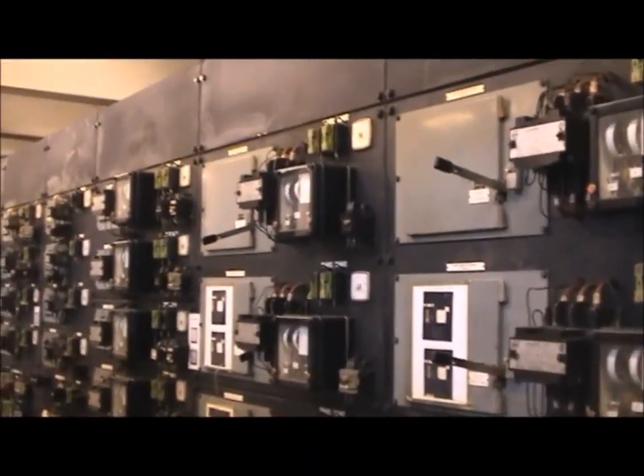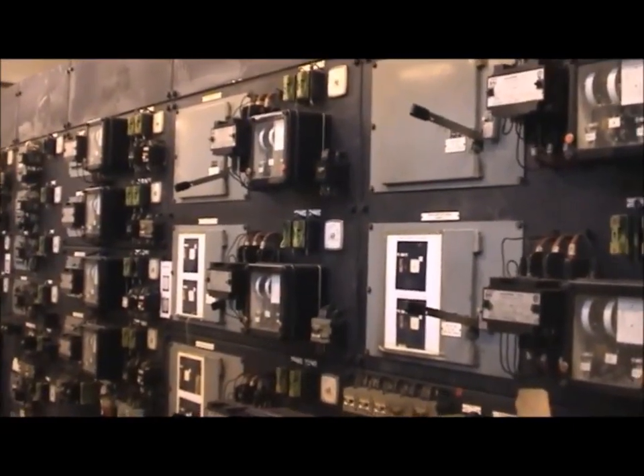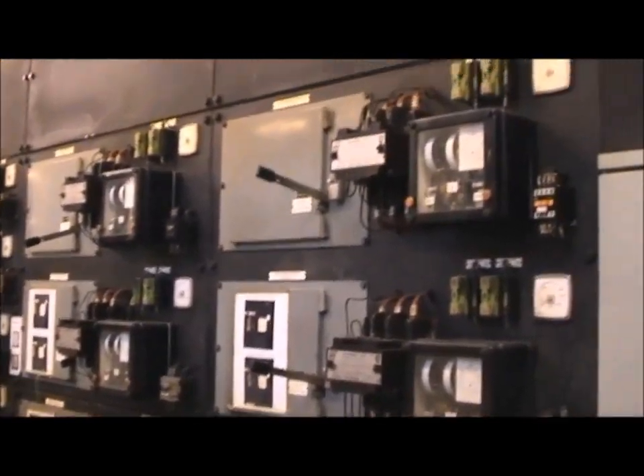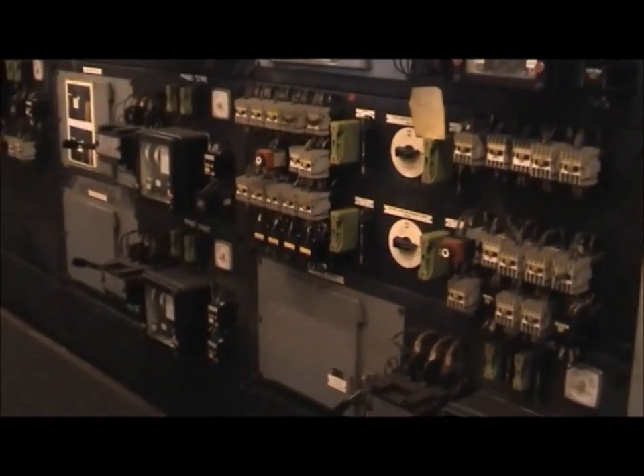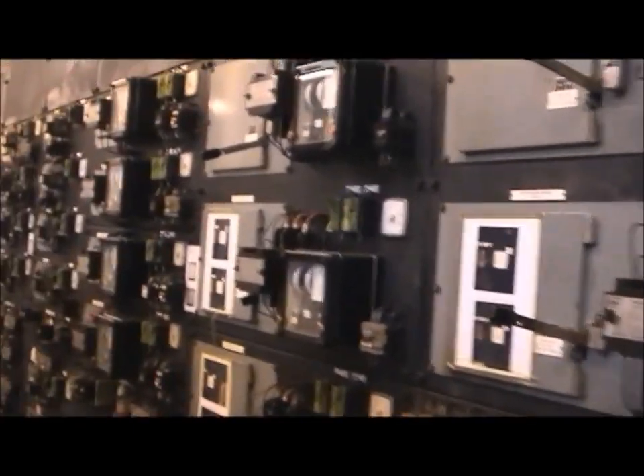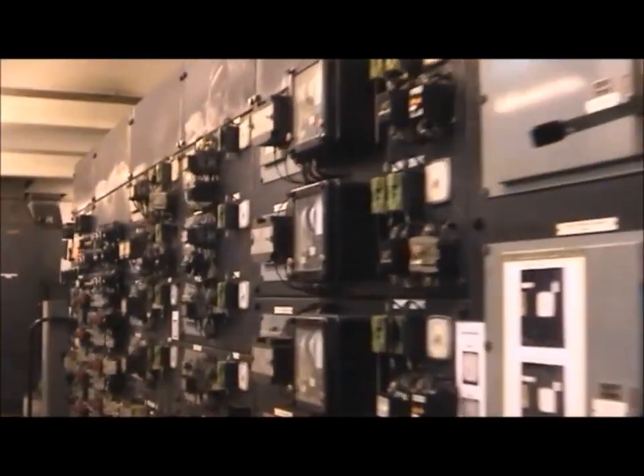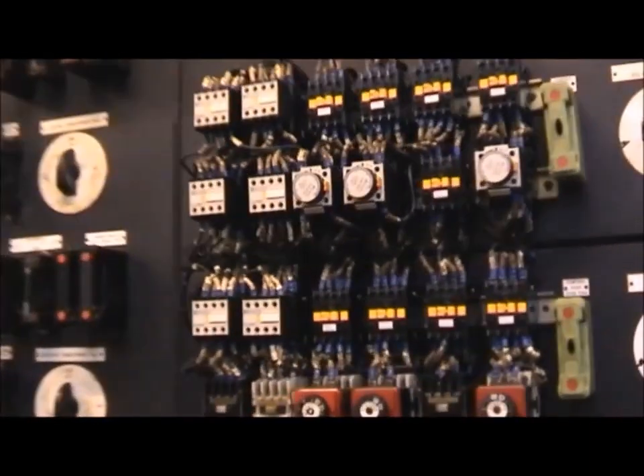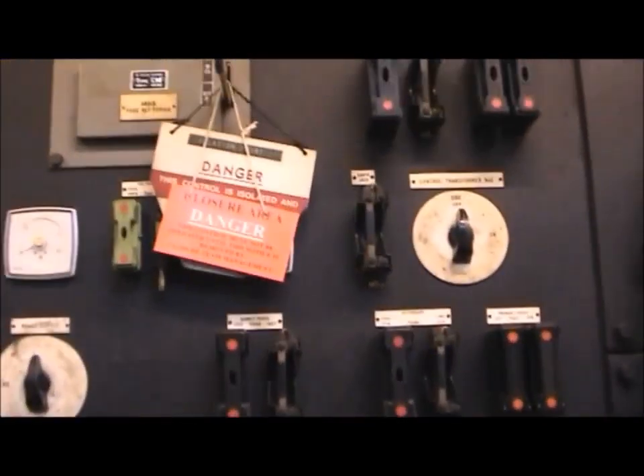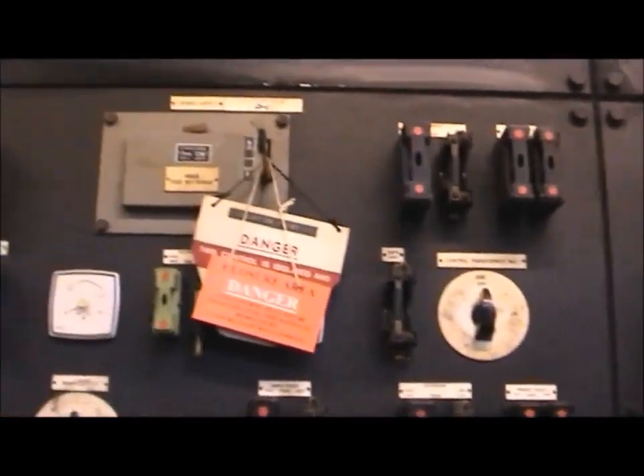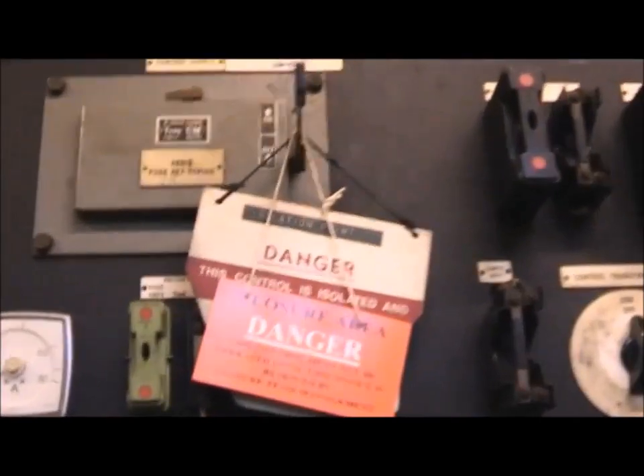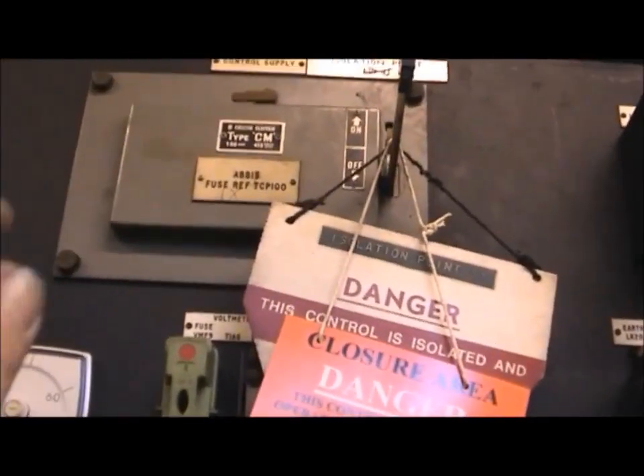These are all the lubrication and hydraulic pump starters, 440 volt, 3-phase machines. The board is live, bus bars are live, no control supply on. We'll now enable the control supply.